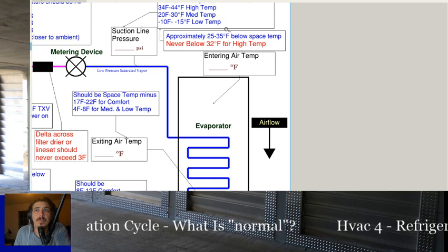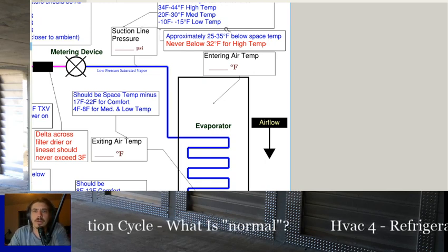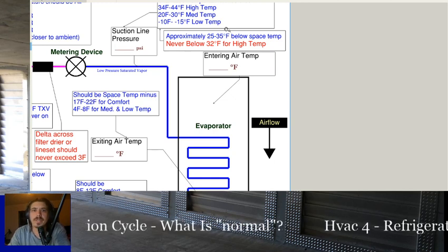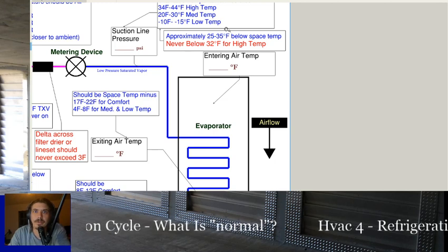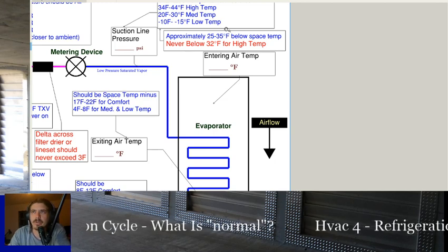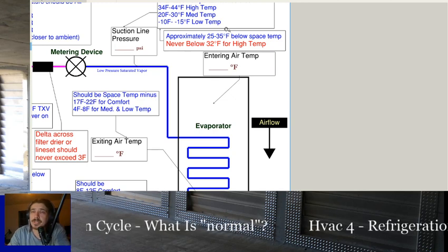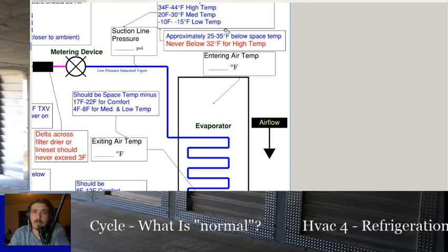With medium temp and low temp systems, we have defrost cycles to thaw those. Like in a heat pump in the winter, we have a defrost cycle because we know it's going to be running below freezing outside, because that's a very cold evaporator trying to pick up heat, right? But if we're running in air conditioning, there's no defrost cycle. So if it starts to freeze, it's going to snowball.